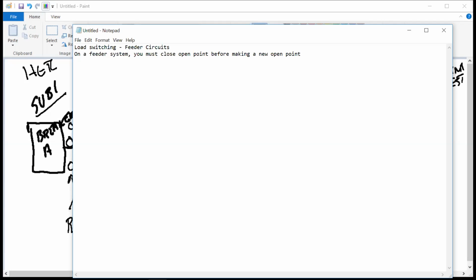Okay, that's critical if you want to maintain power on your feeder circuit. If you first open and then close the other one, you're going to have a line section between 2 opens, and all those customers are going to be dropped. You don't want that to happen on your feeder system. So first, you're going to get your field switch in order, and the dispatchers are going to go through a process of what they call setting the breakers up.